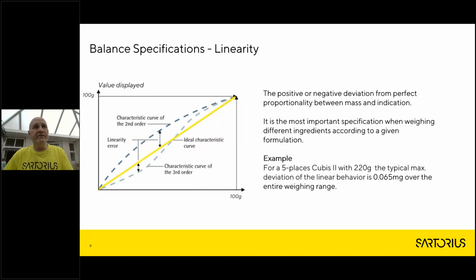The next specification we look at is linearity. Linearity, as you can see on this graphic, is the deviation from the line from 0 to maximum, the straight line between the 0 and the maximum capacity of the balance. Any deviation from that is what we would call linear error. Obviously, we wish to keep this error to an absolute minimum.